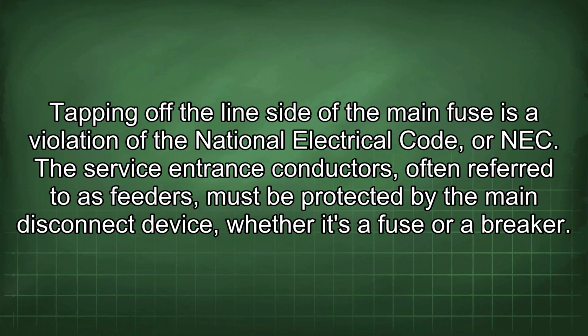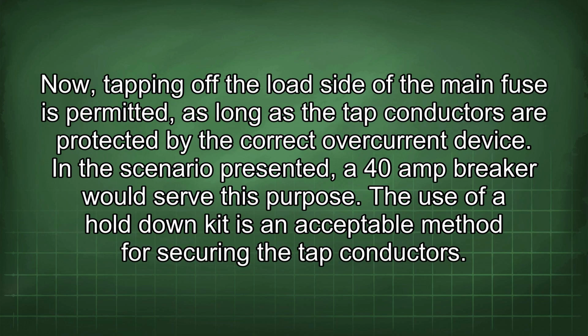Tapping off the line side of the main fuse is a violation of the National Electrical Code, or NEC. The service entrance conductors, often referred to as feeders, must be protected by the main disconnect device, whether it's a fuse or a breaker. Now, tapping off the load side of the main fuse is permitted, as long as the tap conductors are protected by the correct overcurrent device. In the scenario presented, a 40 amp breaker would serve this purpose.